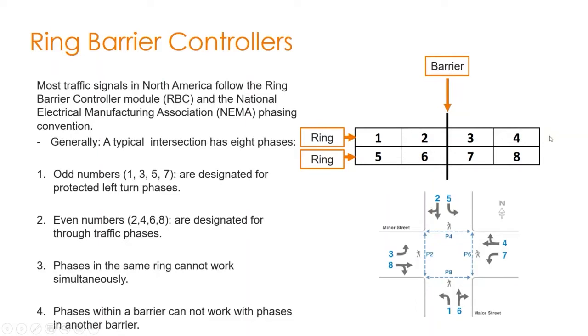Within each side of the barrier, any two phases in the same ring cannot work together. Any two phases that are not in the same ring can work together. That means phase one can work with phase five or phase six, but cannot work with phase two. Similarly, phase two cannot work with phase one but can work with phases five and six.